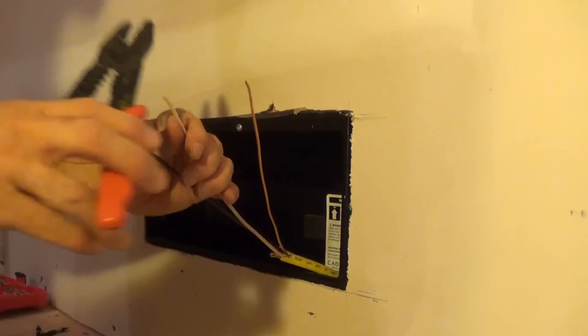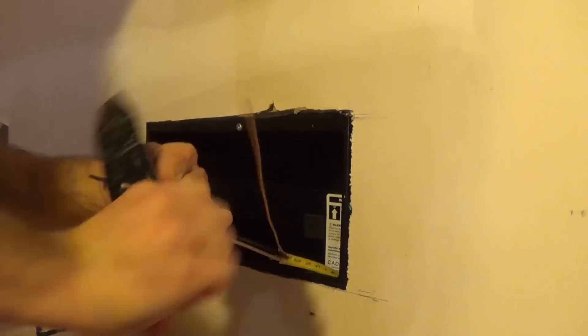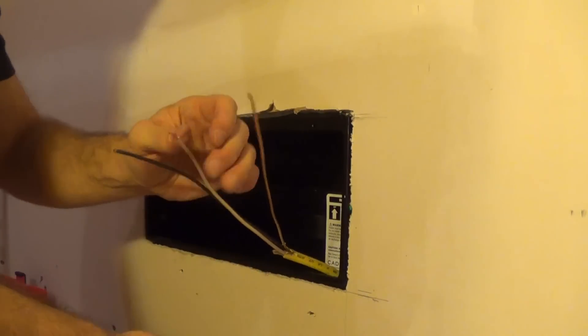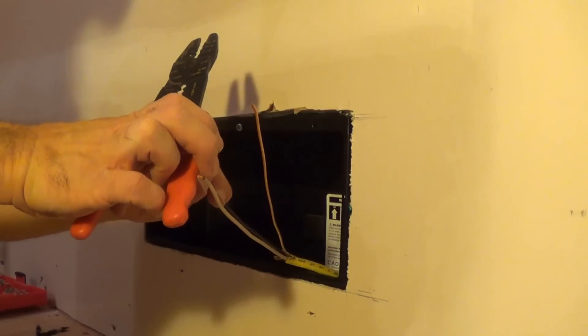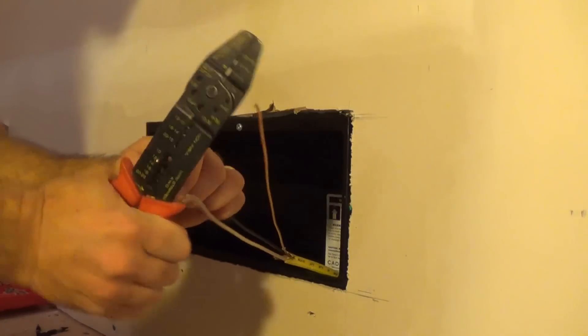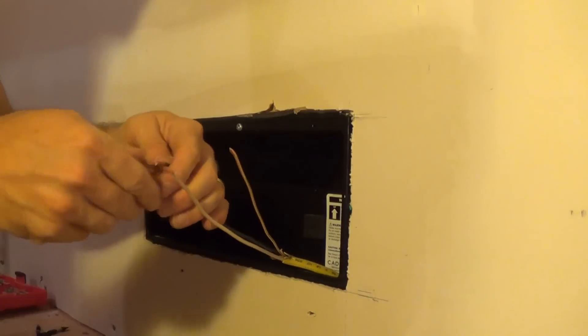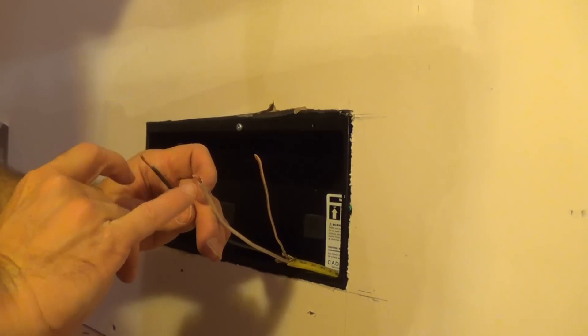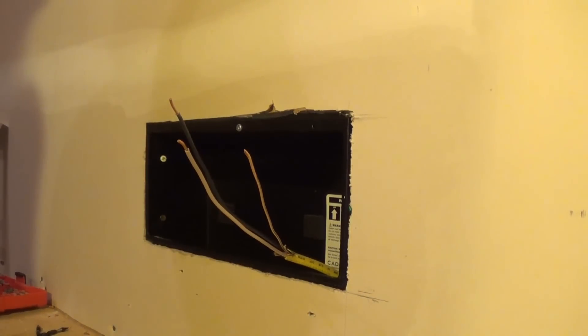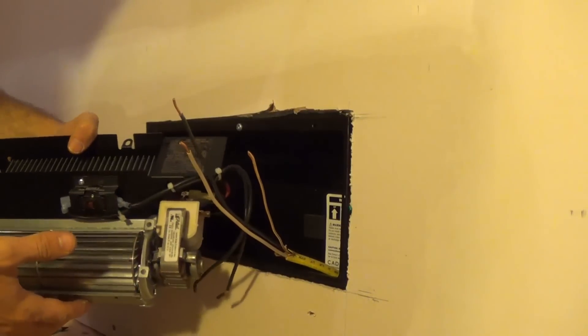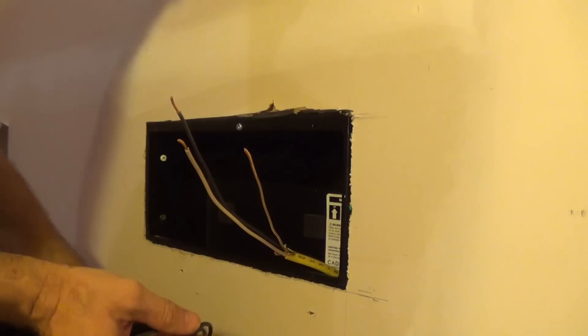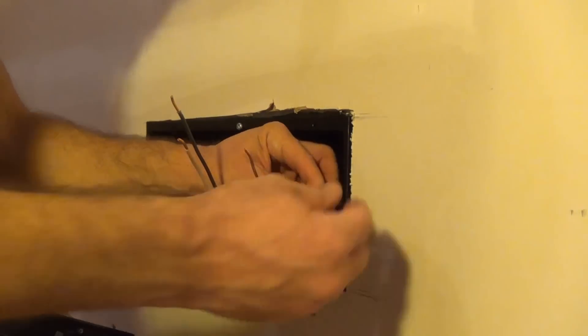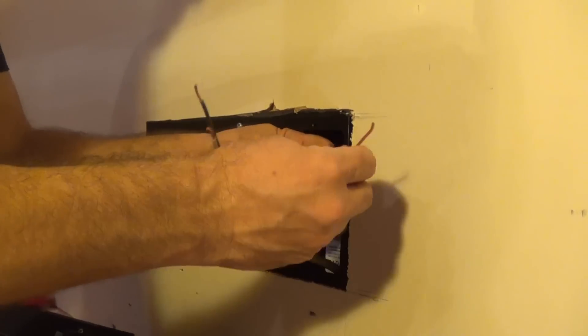The next step is just to wire it all in. I'll go ahead and strip the wire. Now these don't have any power into them yet, so this is just fine to do. I would not recommend doing this with power on. These are going to be the two hots and the ground. There's no common or neutral in this wiring. Here's the heater with the two hot leads, and the ground just goes to the box right here.